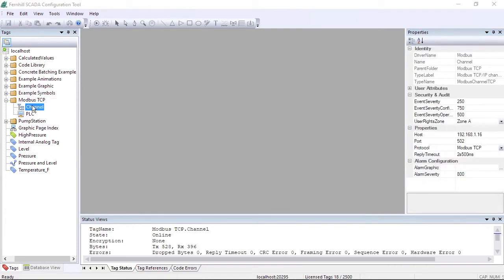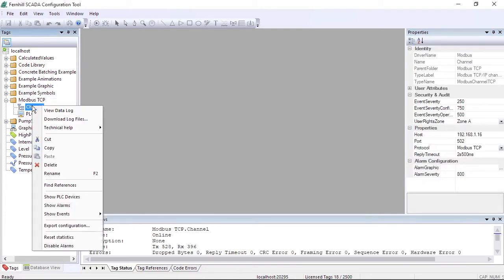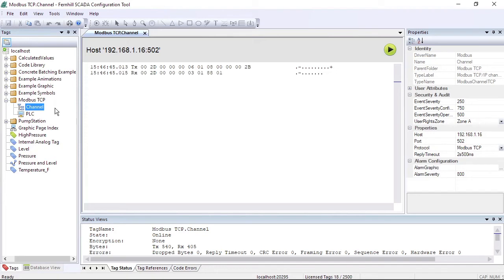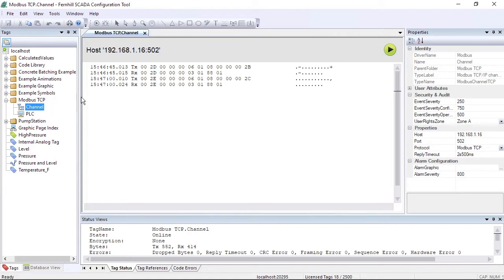If we right click the communication channel tag and select view data log, we can see a live view of the communication with the PLC. With only the PLC tag configured, the activity visible in the log will be limited to an occasional communication check request. By default, this happens every 15 seconds. For now, we'll close the communication log.